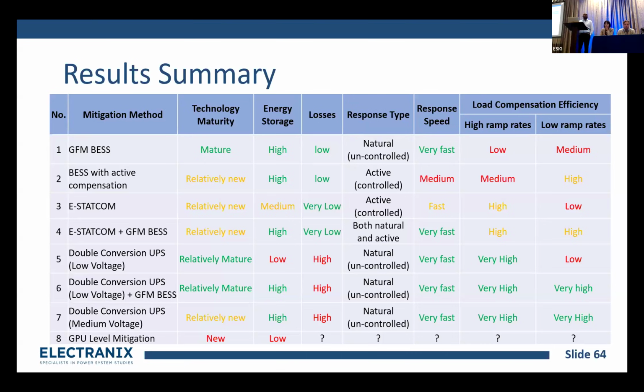If you have a 200 megawatt data center, probably you don't need that. You can get away with a GFM-based or an E-STATCOM plus BESS kind of solution. So it doesn't mean better is always required; it depends on your size, because all these grid requirements are not per-unit requirements. Those are hard-coded numbers: 10 megawatt, 20 megawatt. It doesn't matter whether your data center is 500 megawatt or 1,000 megawatt, you still need to comply with 10 megawatt. That's where the spread comes from. You can pick basically based on your requirement. Thank you very much.